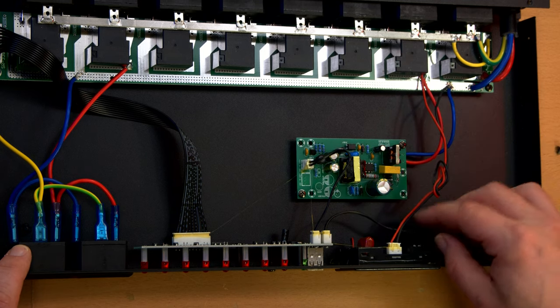In fact, there is some bare metal on the chassis. Let's see if like inside one of these screw holes where it's not powder coated, if I get continuity between live and ground and we see 120 volts. Yes, we do. Okay. So the chassis is grounded. That's always a good thing. I know I could have tested continuity rather than actually running 120 volts through that. But for those of you that perhaps would just prefer to see straight up continuity, I will touch the ground bus bar and there we go. And we got 2.3 ohms.